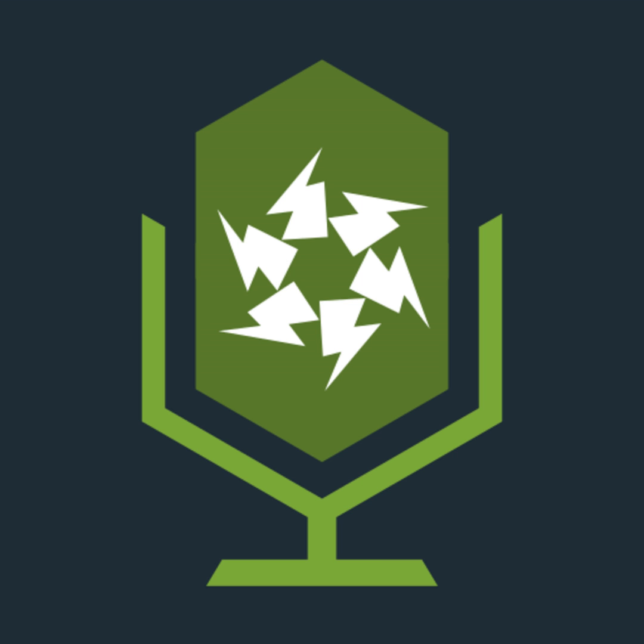So if your main earthing terminal is outside of the board, you don't connect one between the protective conductor and the exposed conductive part. Okay, so you can see how they can catch you out with a question from that if you're not sure. You may have in your mind, oh, you put one on the gas, you put one on the water. Well, those are both option 2 there. They're both extraneous conductive parts. You need to always think a little bit deeper than that. And we have labels for bonding connections. We have non-standard colour again. And we have alternative supplies.